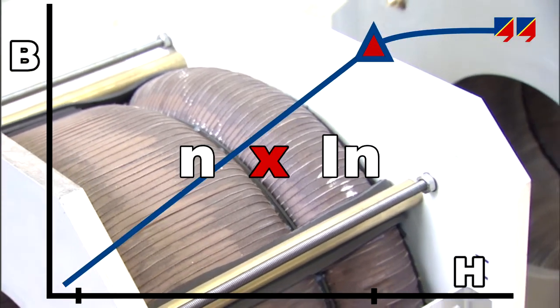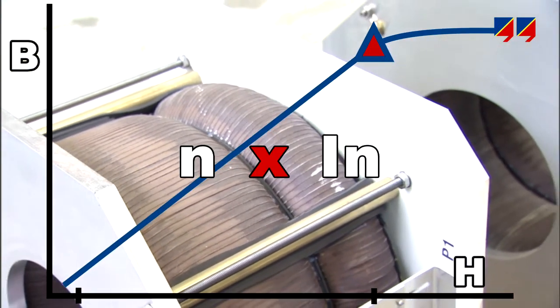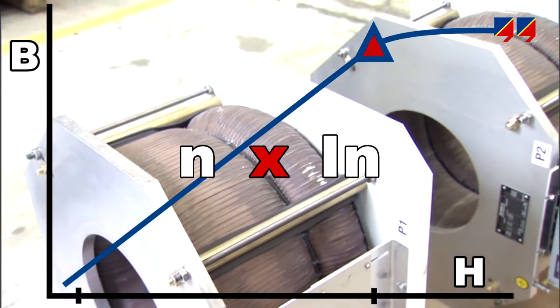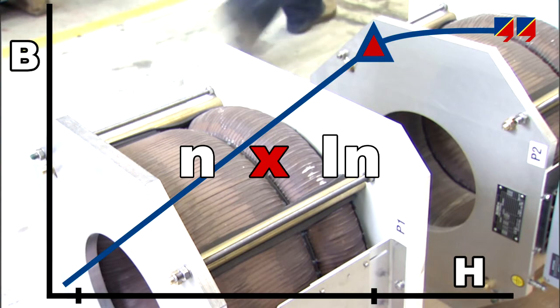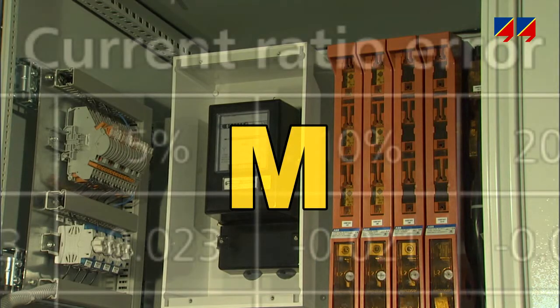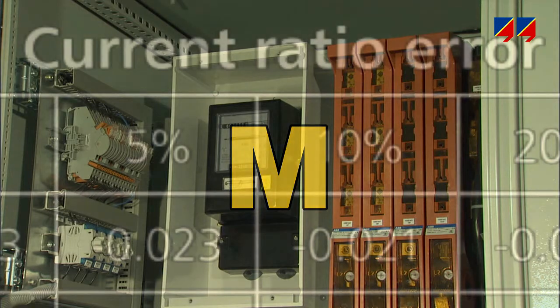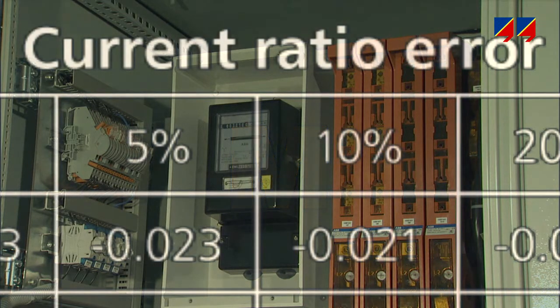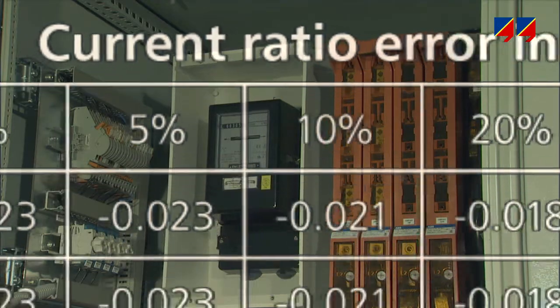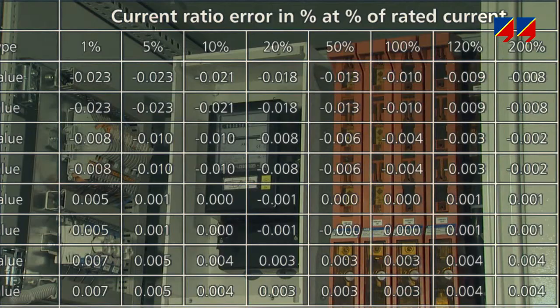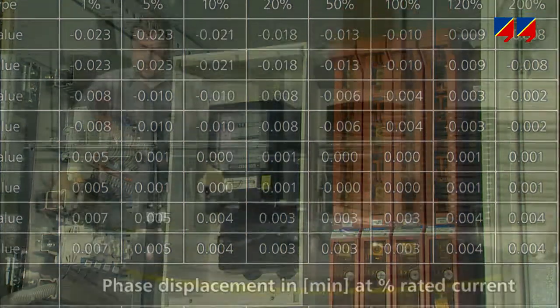The secondary current produced by the CT must be proportional to the current flowing in the power system over the whole range within a defined accuracy. Accuracy is the crucial criterion regarding metering CTs, as the financial consequences of incorrect billing may be very significant. The applicable standards define the ratio and phase accuracy which the CT has to provide in its specified operating range.